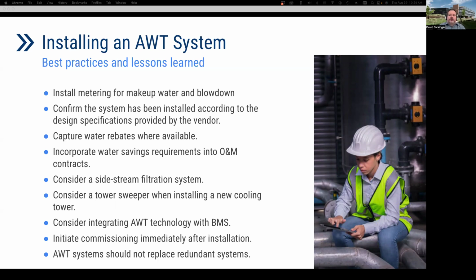Suggest working with the local water utility to capture any water rebates where available, and also incorporate water saving requirements into O&M contracts. Some other good practices: consider a side stream filtration system that has a backwash glass media system for open cooling towers. Again, towers are prone to collect dirt and debris. Along those lines too, GSA recommends considering a tower sweeper when installing a new cooling tower to deal with sediment that collects at the bottom of the basin. And it is good practice to try to integrate the AWT technology with a BMS, building management system, to help monitor performance.